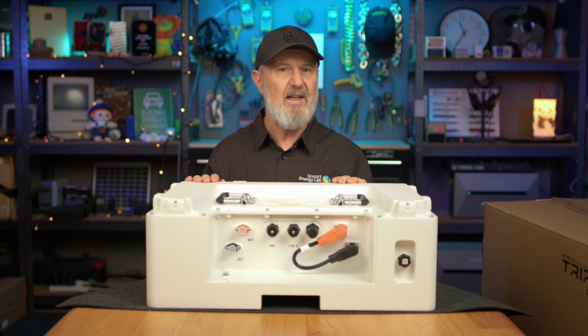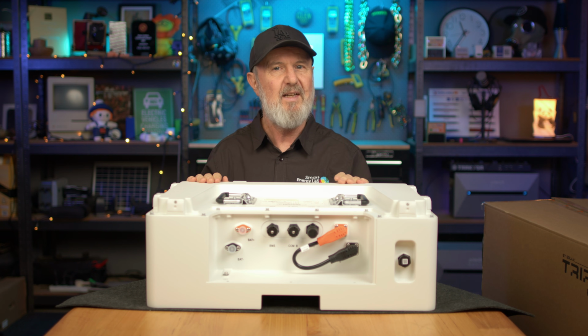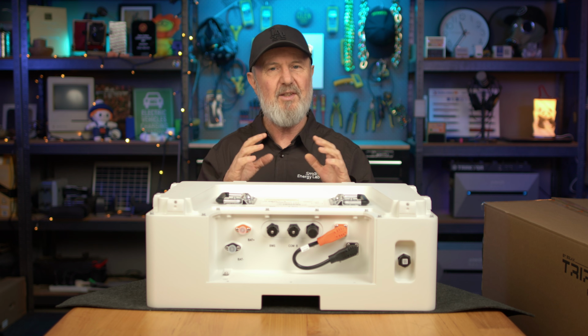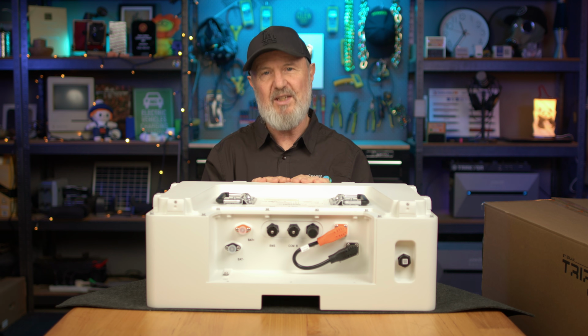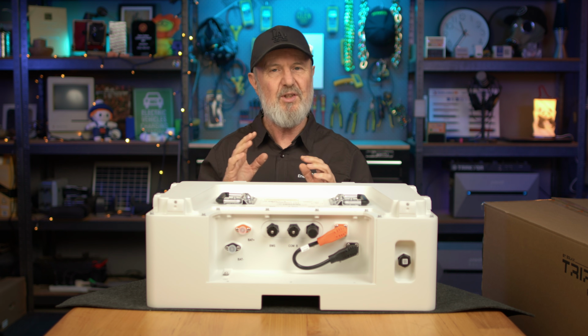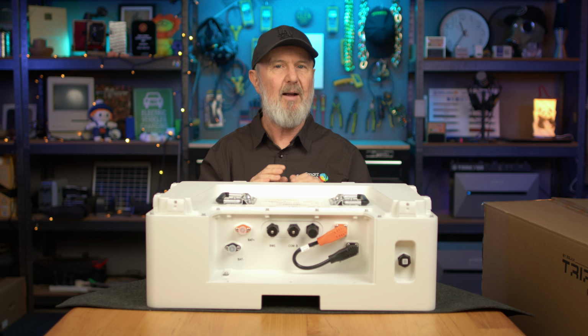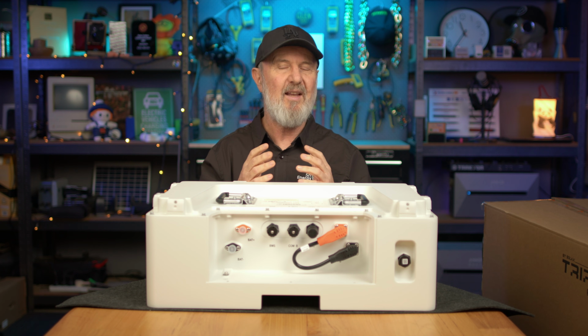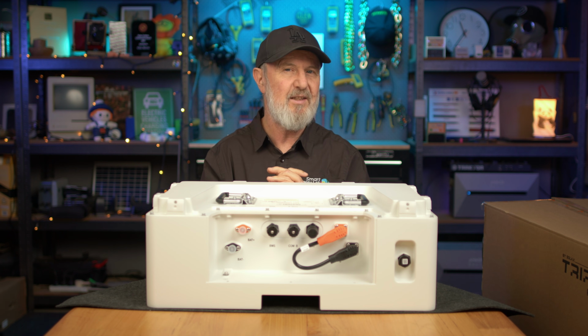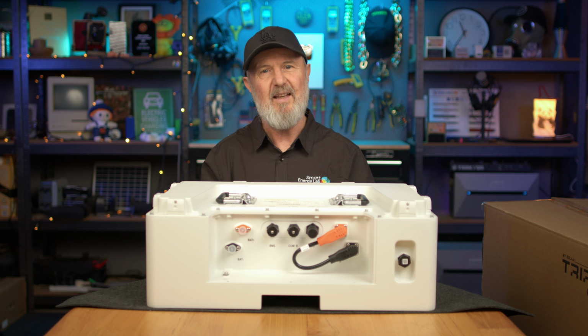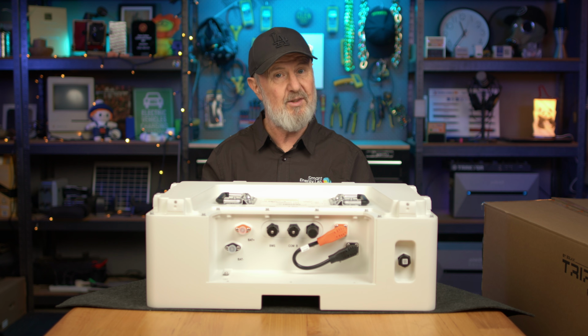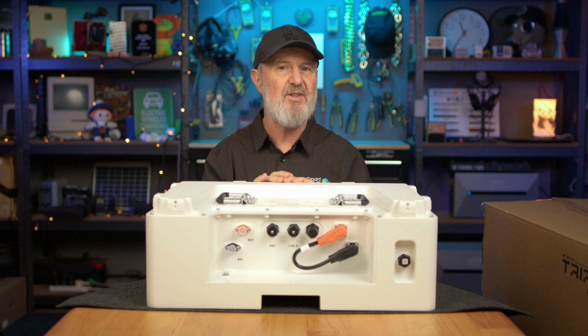And a rapid charge. You can charge these very fast, and with a 3-hour equalization, because they have a special optimizer that allows the battery modules to be individually charged. So you might actually have some which are slightly older or slightly newer, and that means that their capacities are slightly different. But with the optimizer, it allows them to charge to their maximum capacity independently. That's a good feature, particularly if you're upgrading a system with old and new batteries mixed together.